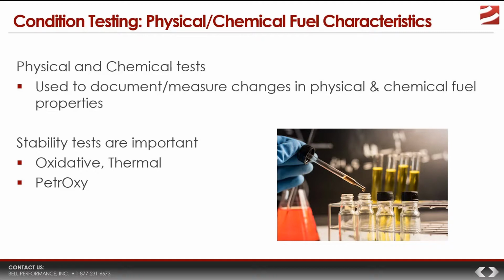Well, that makes the fuel hazy, increases the haze. It increases the amount of total suspended solids. It can reduce cetane rating in diesel fuel. That's a big one. We already mentioned that in gasoline, because of the consumption of the lower end carbon molecules, you can change the vapor pressure. So it can have those and other detrimental physical changes to the fuel.